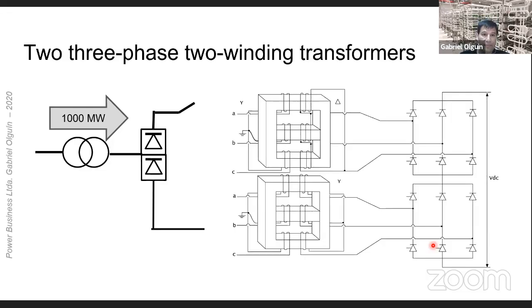Here you have the converter transformer made of two three-phase two winding transformers. This is a converter transformer system formed by two three-phase two winding transformers. Both primary windings are Y grounded. The secondary winding of the upper three-phase transformer is feeding the high voltage 6-pulse converter group in delta. The low voltage 6-pulse group is fed by the secondary of the lower transformer in Y ungrounded.